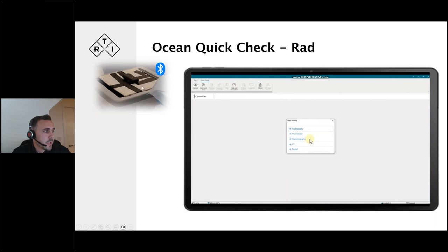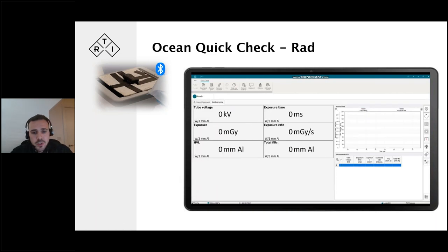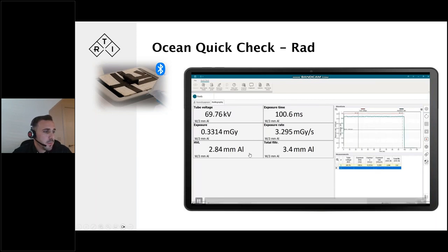As I mentioned, this is a Piranha Multi, which can be used across all the X-ray modalities, different kV ranges, different applications. All we have to do is tell the software what modality we want to run in, so we're going to select radiography. Then the software auto-configures to that modality, so we only see the parameters that we need to see for this modality.